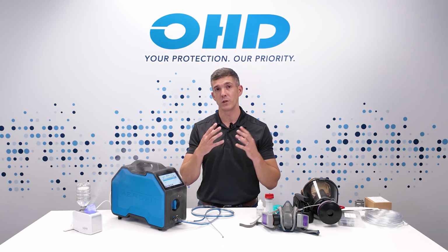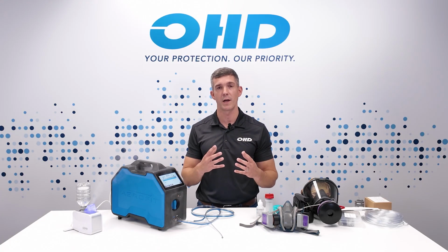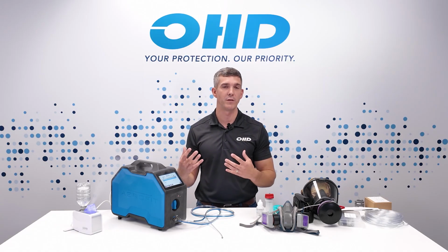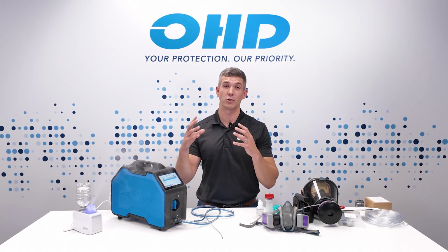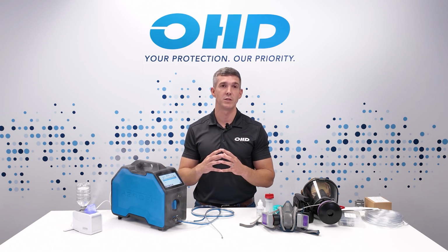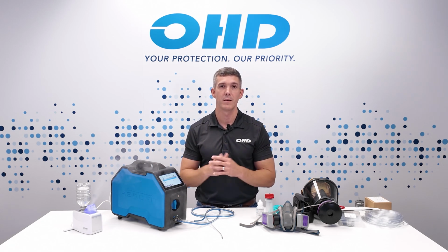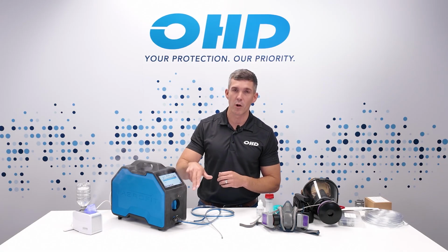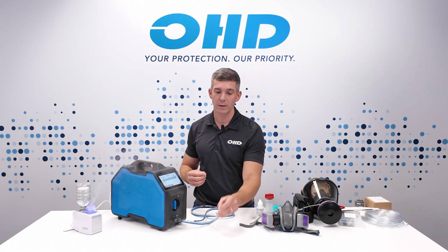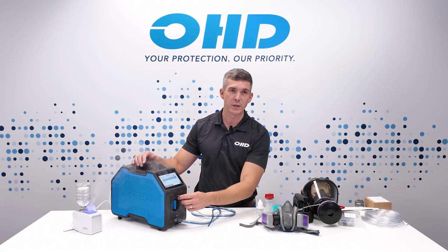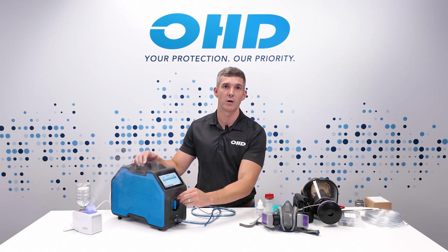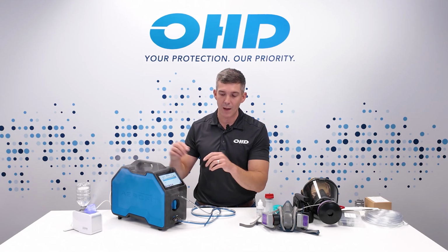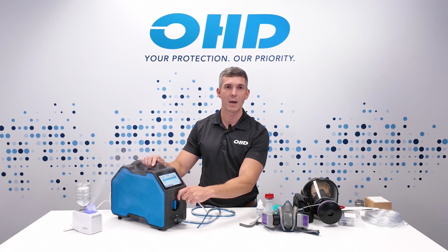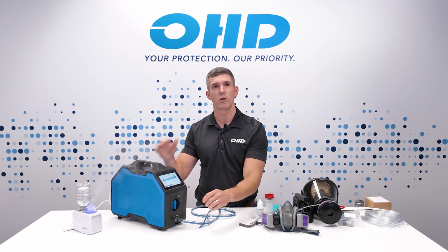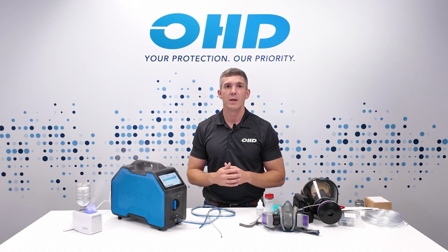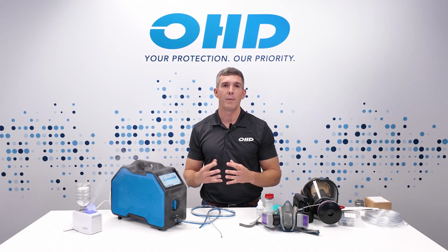You also want to reference what I just talked about on high and low particle concentrations. That can have impacts on your daily verification, especially if your particle concentrations are too low. Too low concentrations can make daily verification much harder to pass. And then finally, you want to make sure that your zero port is connected up correctly, and that your tube set, when doing the zero port check, is fully pressed onto the port all the way in. So any very minimal connection could let in a leakage from the environment, causing a failure on daily verification. So these are some of the main troubleshooting aspects.